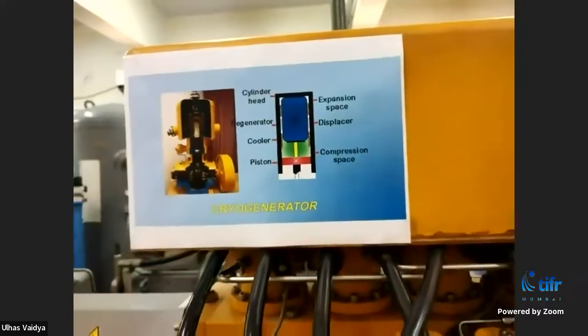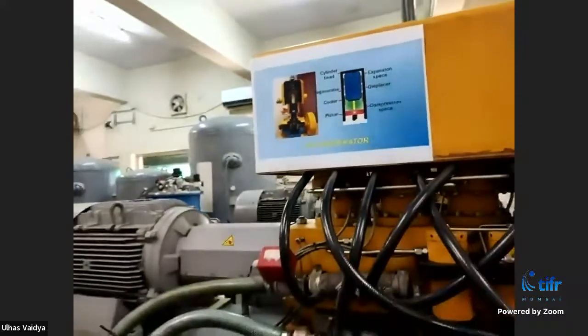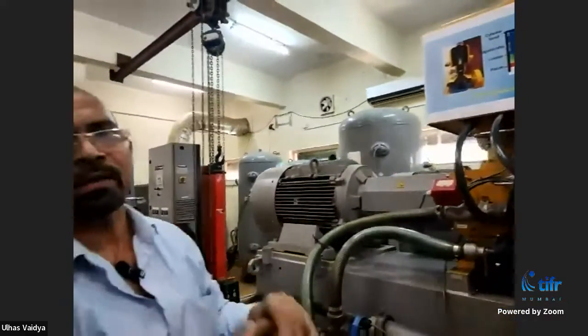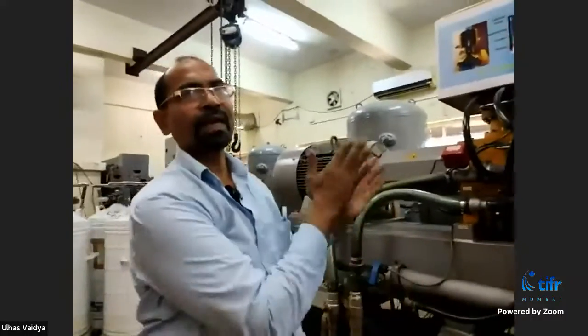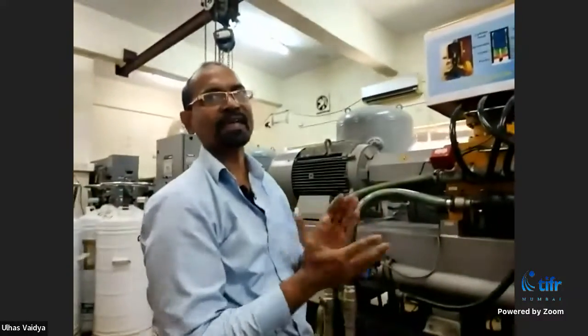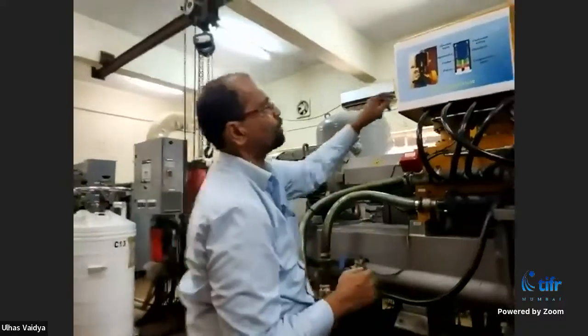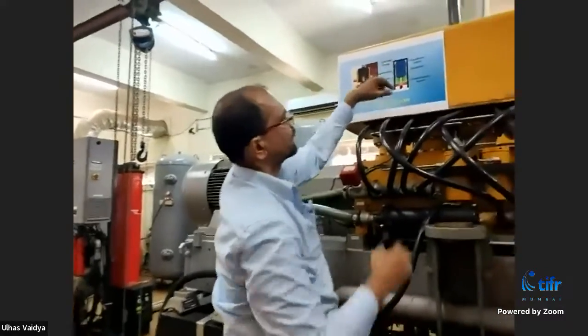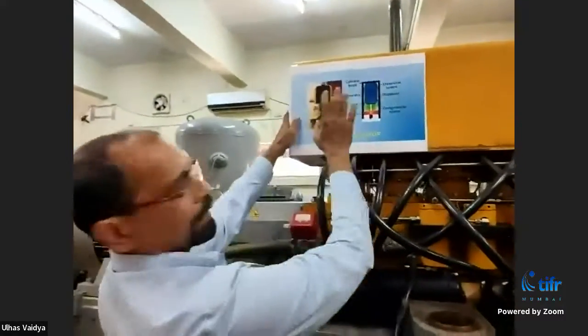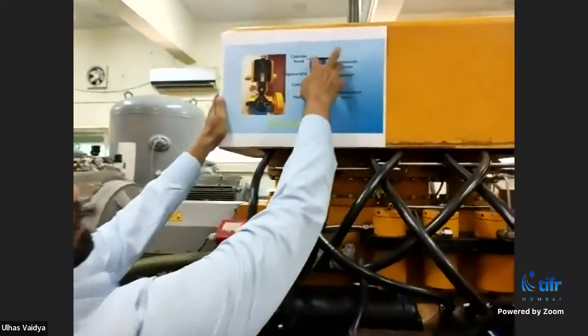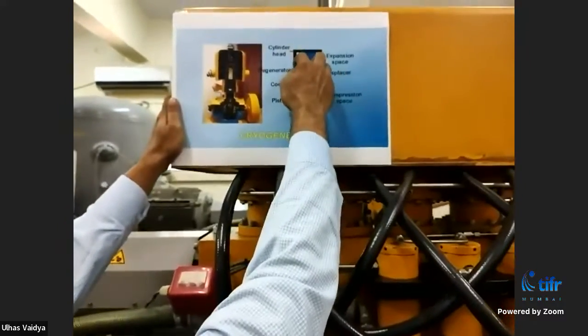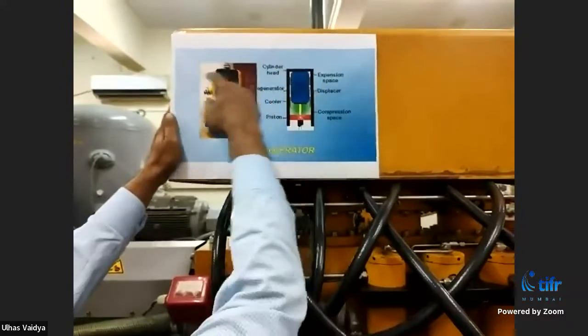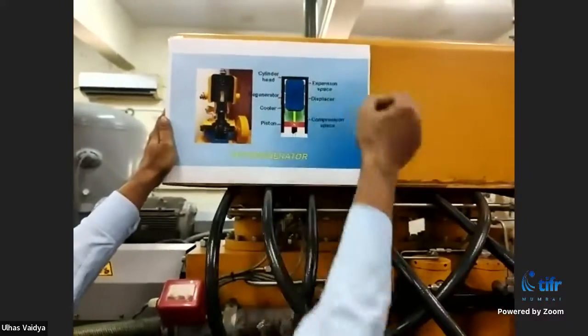So at each and every cycle, the temperature goes down and down, and within half a minute we can reach minus 200 degrees Celsius. That temperature is absorbed by the outside gas in this chamber, in the condenser header, and the liquid air is cooled and forms liquid nitrogen.